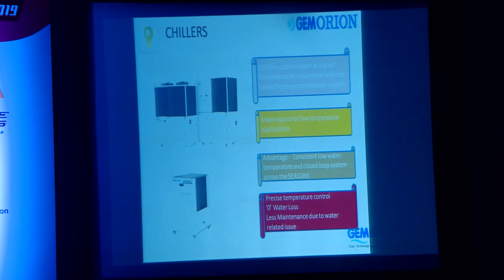So now we are coming to chillers. See, currently customers who are using multiple installations, multiple machines are looking at some kind of a centralized cooling system, and the centralized cooling system involves so much of piping, run through pipes, electricals, cabling, distribution, and then we have the problem of scaling as well, which we have to address. So adapting to get through all this, what Japanese have been doing throughout is to use dedicated chillers for different machines, or maybe one chiller for 2, 3, 4 machines, so that it can be cooled in complete closed loop. Cooling requirement will be taken care of, and there is no scaling and zero water consumption.